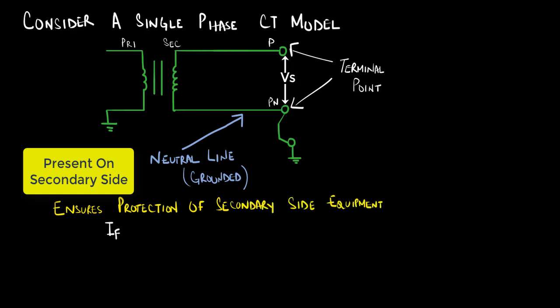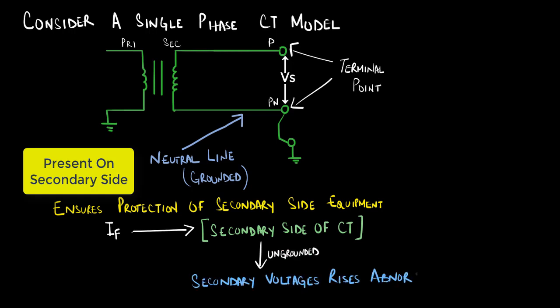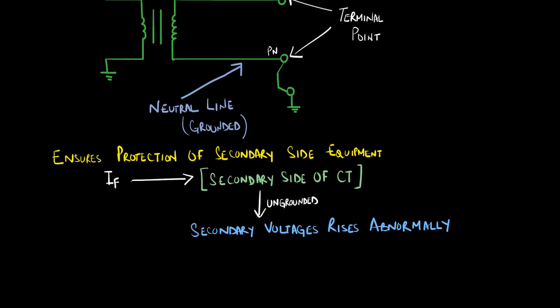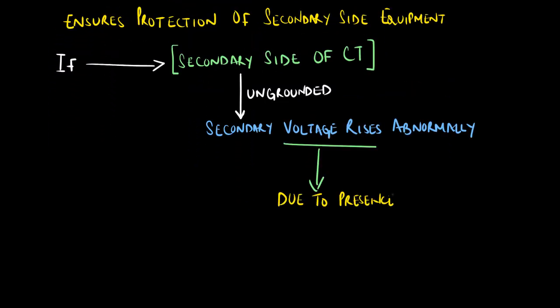On the other hand, if we had left the CT ungrounded, this would cause the secondary voltage, Vs, to rise to abnormal values. The voltage rise is due to the presence of stray capacitances.